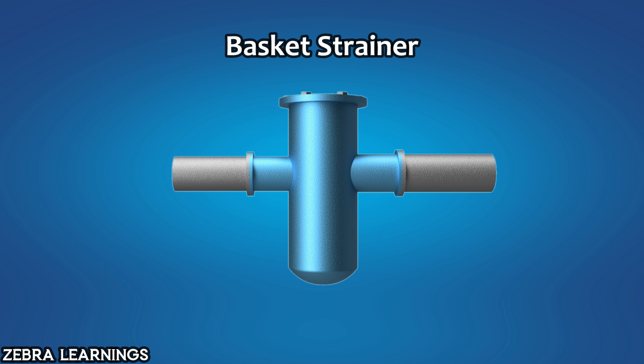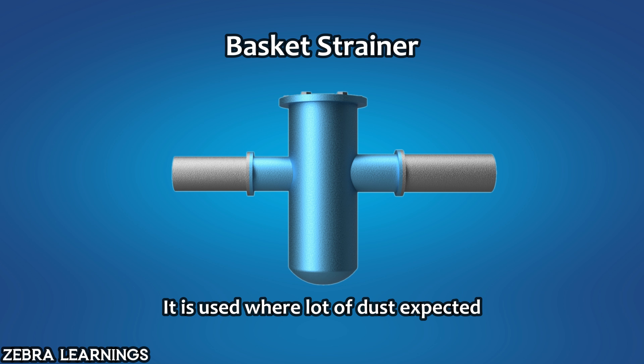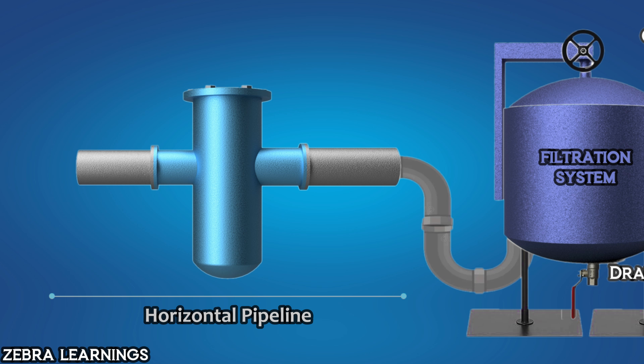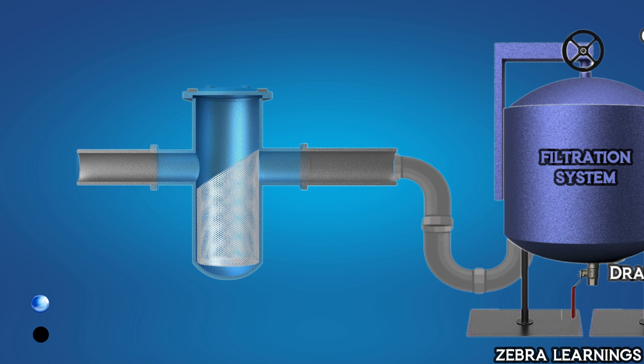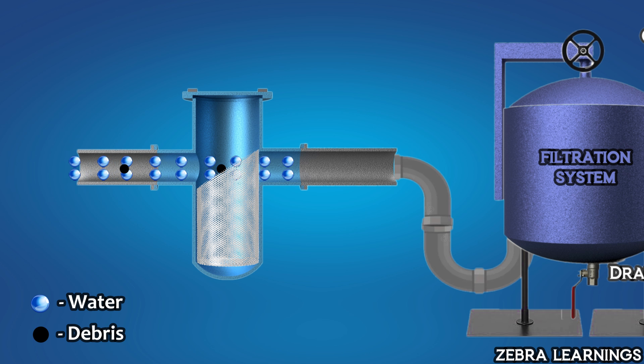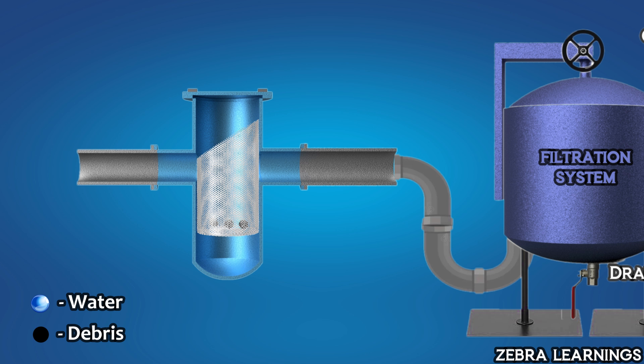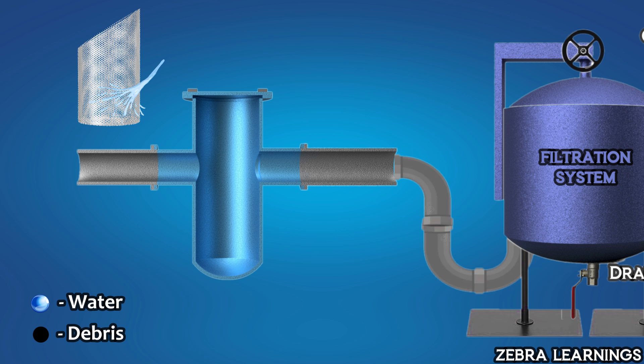Next, let's understand how a basket strainer works. Basket strainers are used in systems where a lot of dust is expected. For example, they are used in filtration system pipelines. A basket strainer can only be installed in a horizontal line. When water flows through the pipeline, it travels through the strainer. As it travels, all the debris in the water gets filtered and stored in the strainer. Then the filtered water goes to the pump. We can then remove the strainer and clean all the particles that are inside it.